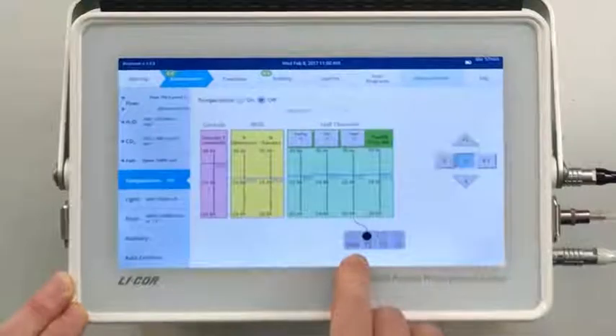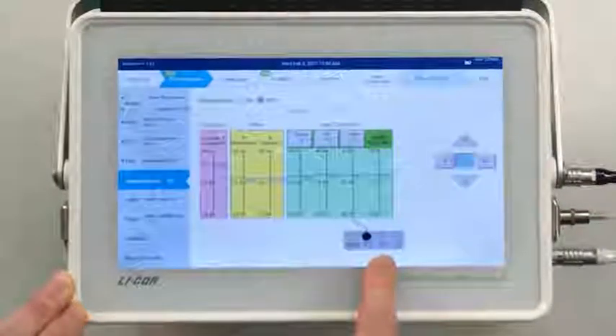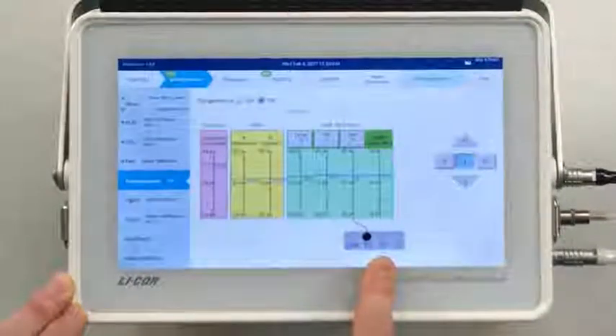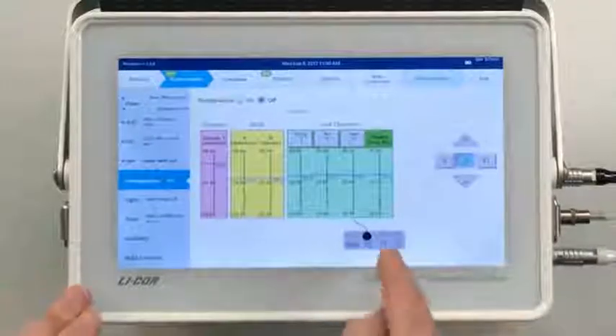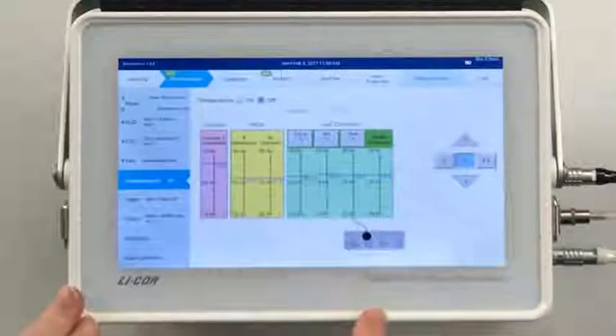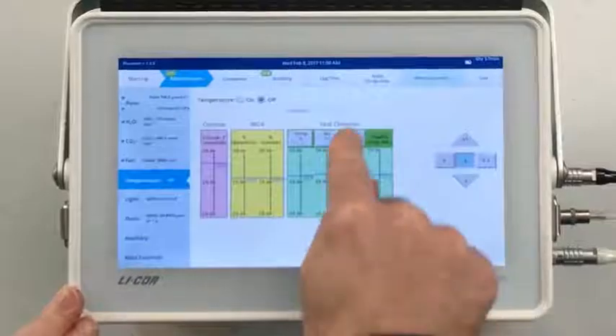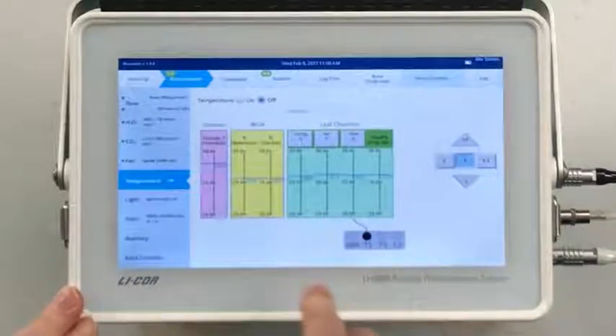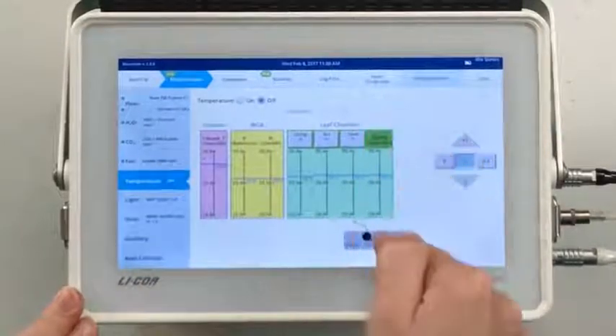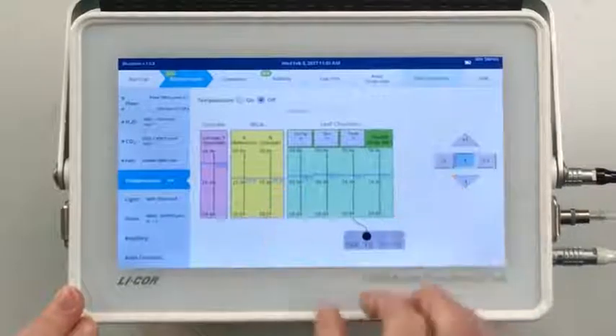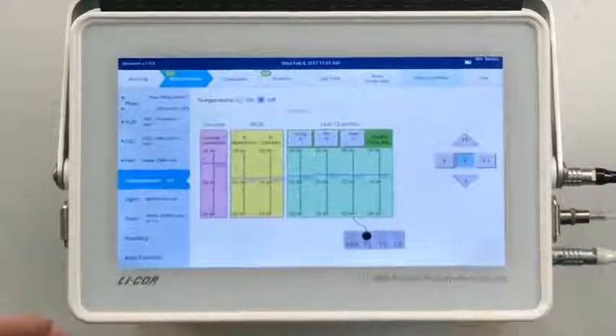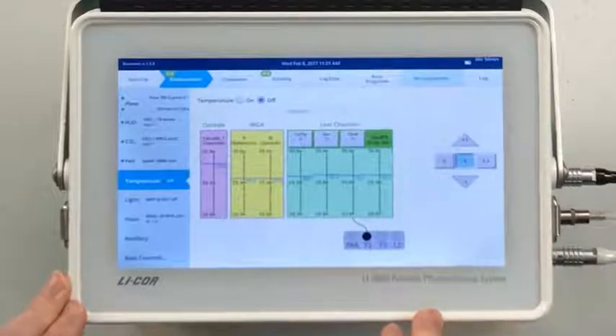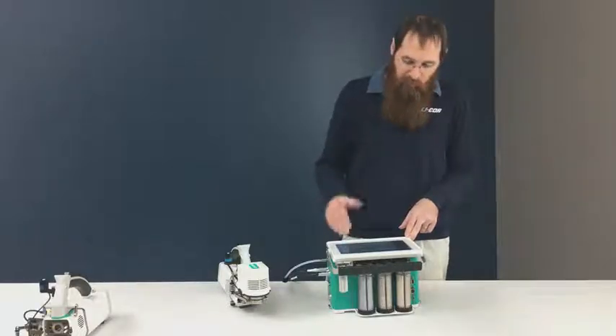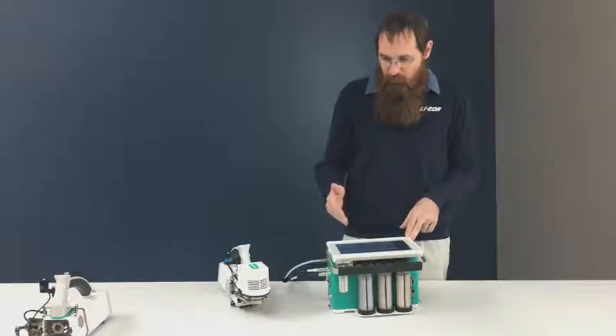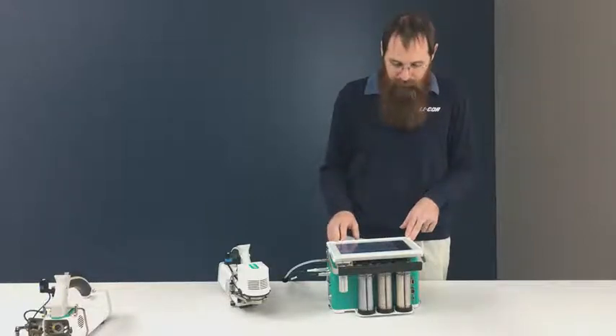Okay? Temperature control, I said I'd come back to this, right? We have the option for T1 or T2, right? These are leaf temperature sensors. If I have one sensor and I plug it into T2 and nothing in T1, the instrument will automatically map T2 to leaf temperature. If I have two sensors plugged in here, I'll get an extra column in this little green section of the diagram that shows me the measurements from T2, and then it'll give me some options for what to do with those measurements. Whether to map them to leaf temperature or to use an average of the two values.